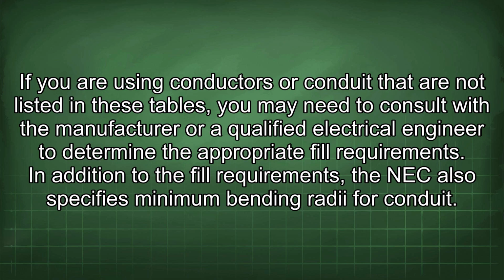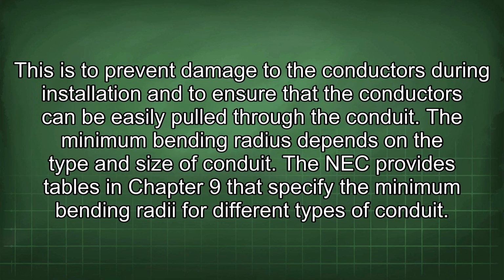In addition to the fill requirements, the NEC also specifies minimum bending radii for conduit. This is to prevent damage to the conductors during installation and to ensure that the conductors can be easily pulled through the conduit. The minimum bending radius depends on the type and size of conduit. The NEC provides tables in Chapter 9 that specify the minimum bending radii for different types of conduit.